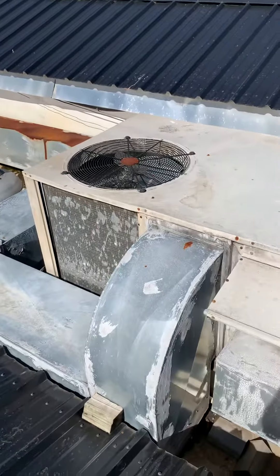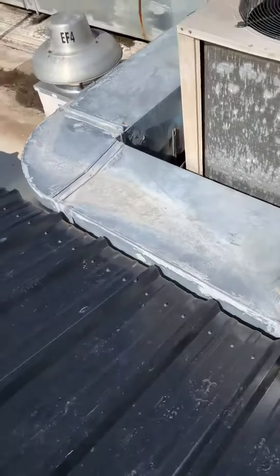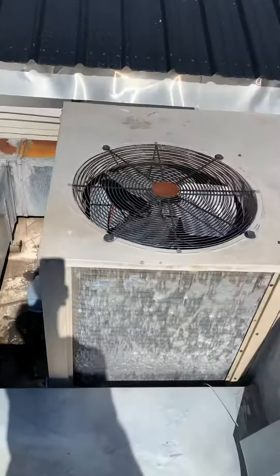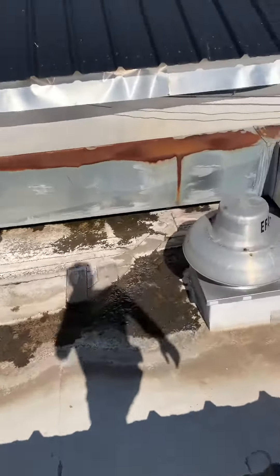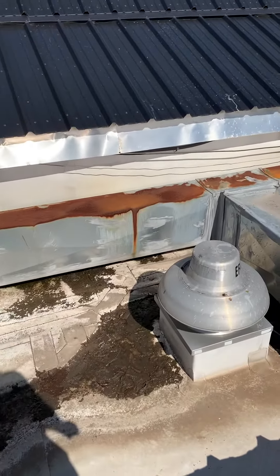Got dimensions of this. Supply comes out, runs over, and then T's off heading back over here, and then stops right about there, covering more of this patio area with the help of another five-ton split.